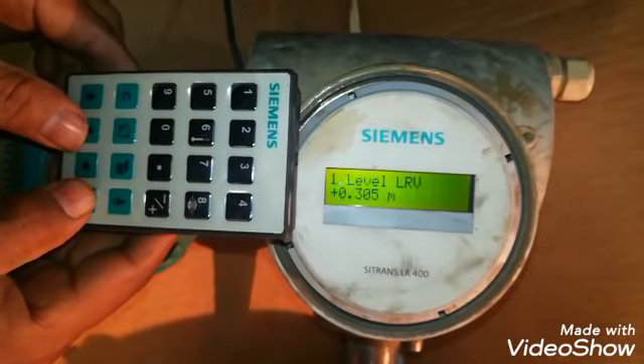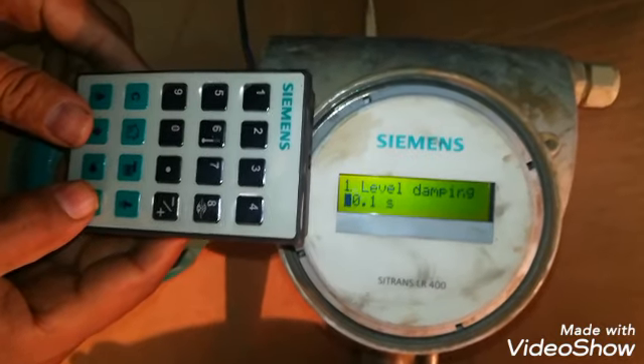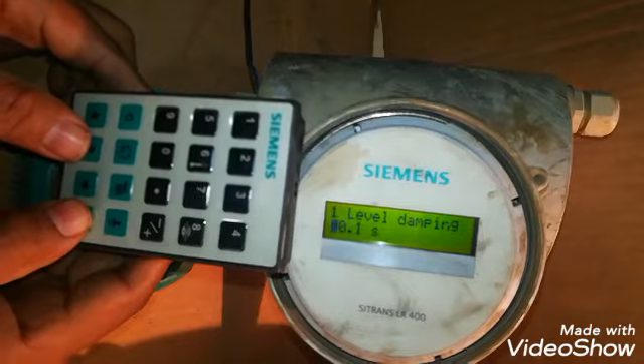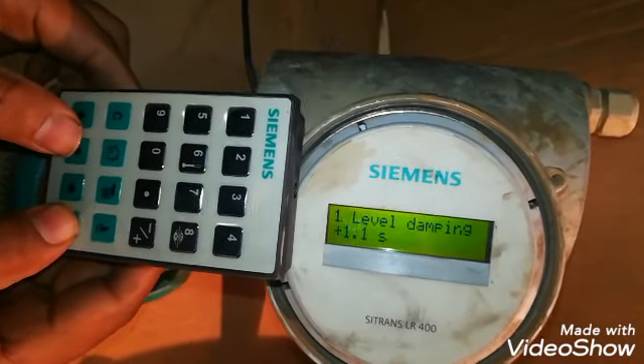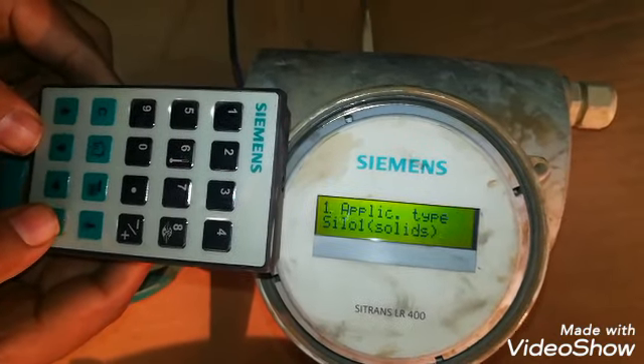Now I will change the LRV. I want 4 milliamps at 0 meter. I will make it 1 second damping.